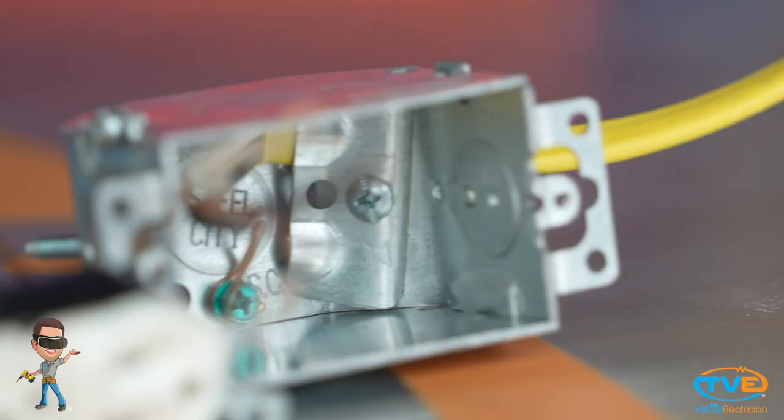Whenever you have equipment grounding conductors in a metal box, you need to attach them to the box using a green grounding screw or grounding clip.